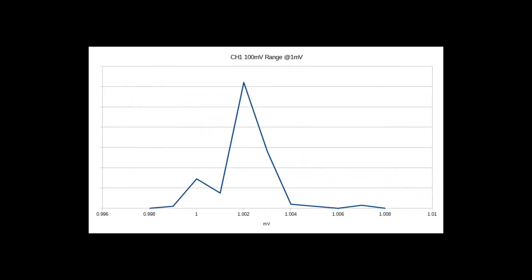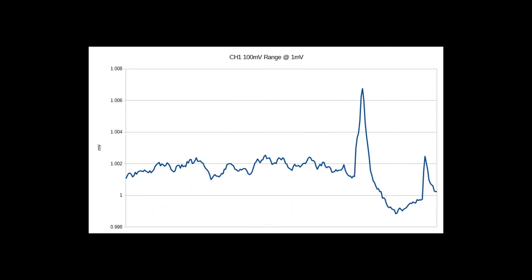The noise on the 1 millivolt reading is plus or minus 5 microvolts, but there is an offset of 2 microvolts from the expected reading. There is no upward or downward trend in the data over time, but there are two spikes and a dip just before I stop recording.